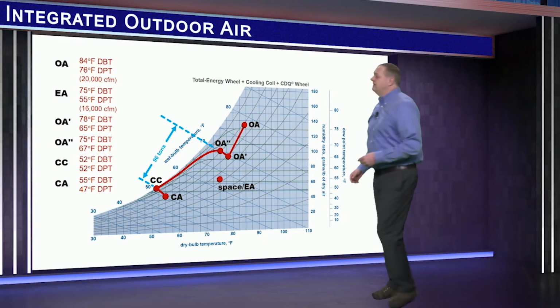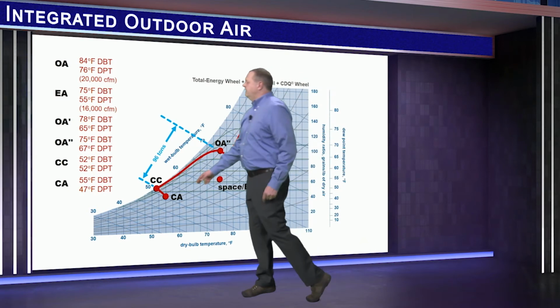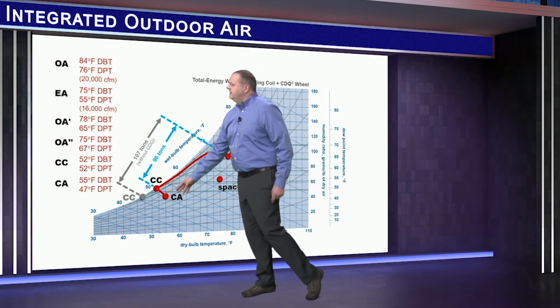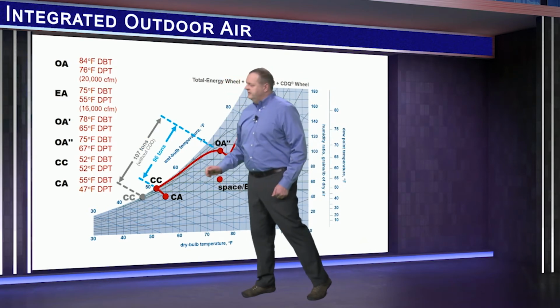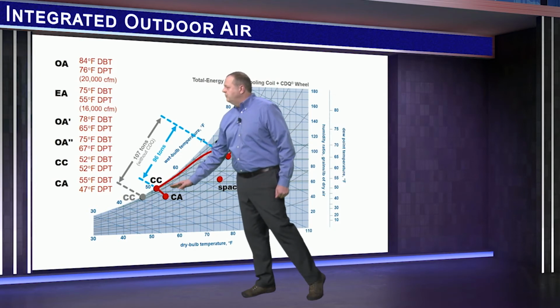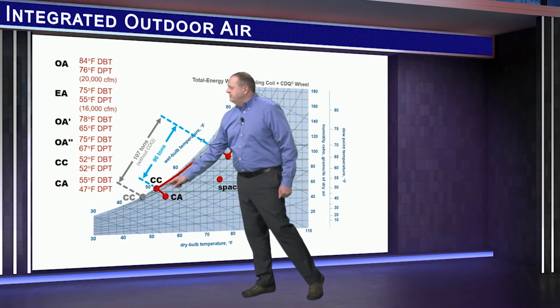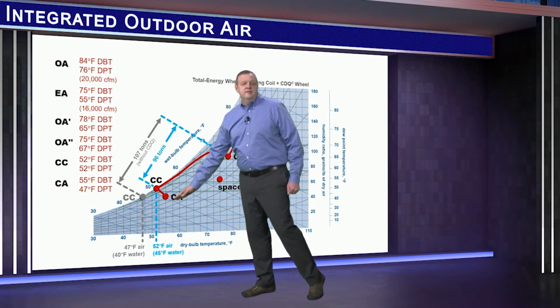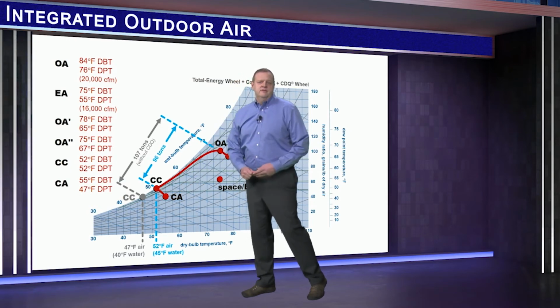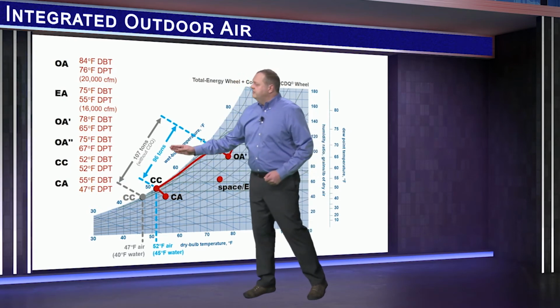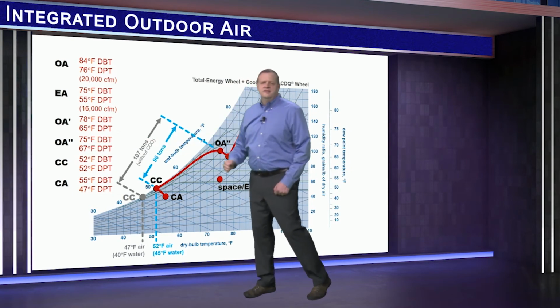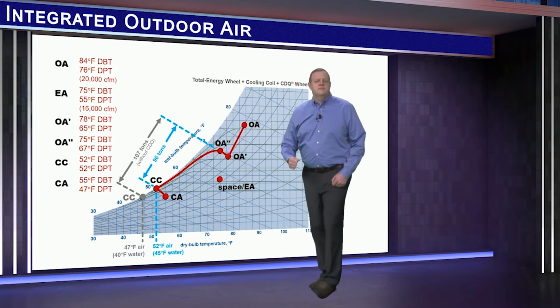After air leaves the cooling coil, it passes through the downstream side of the CDQ wheel. This desiccant absorbs water vapor, further dehumidifying the air. In this example, the cooling coil need only dehumidify to a 52-degree dew point because the desiccant wheel dehumidifies it the rest of the way to 47. So the coil load is reduced to 96 tons compared to 107 tons without CDQ.